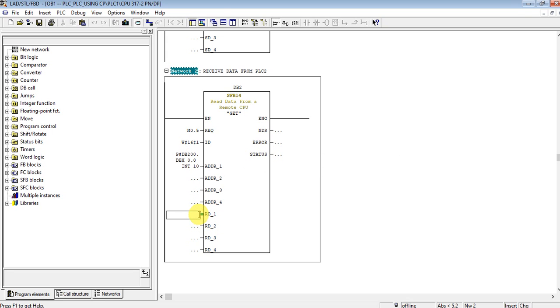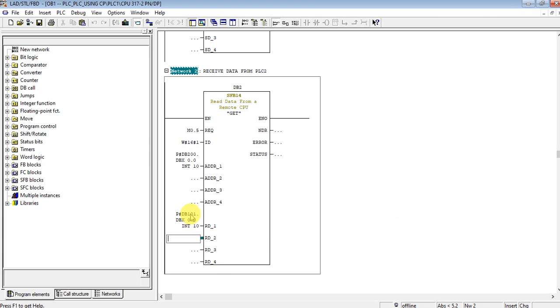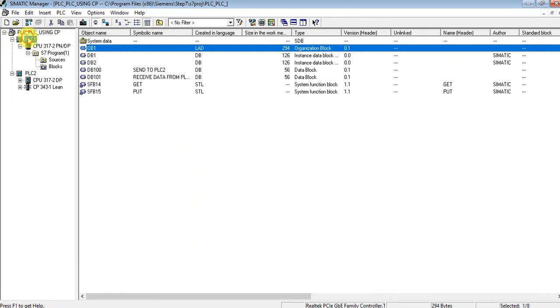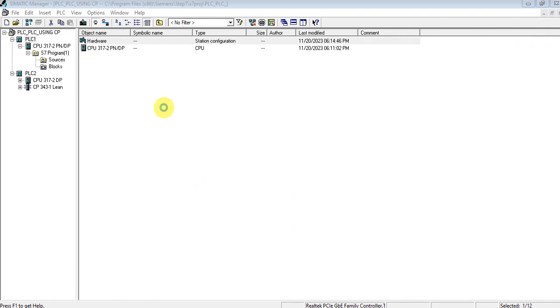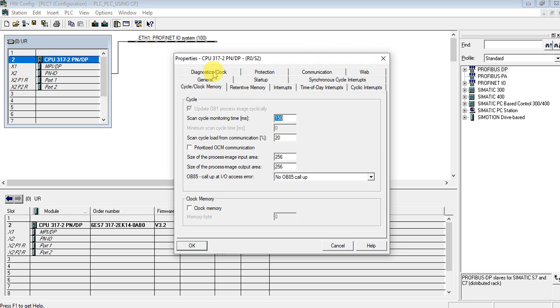For the GET instruction — receive data from PLC2 — the system function is used again. The connection is the same. The source data on PLC2 is DB200, and where I am going to save it on PLC1 is DB101, starting from byte 0, integers 10. Everything is done for the programming side. Now I need to activate the clock memory — that's a mistake I forgot earlier.